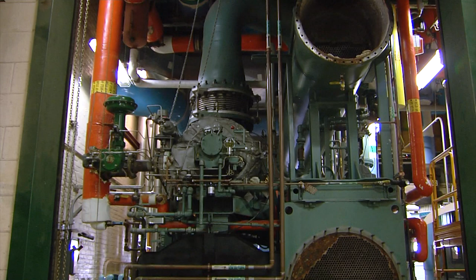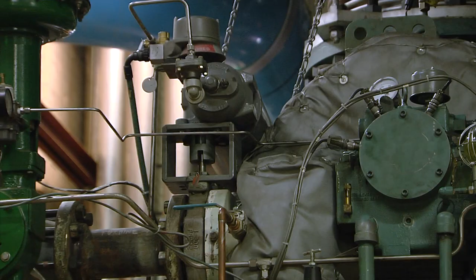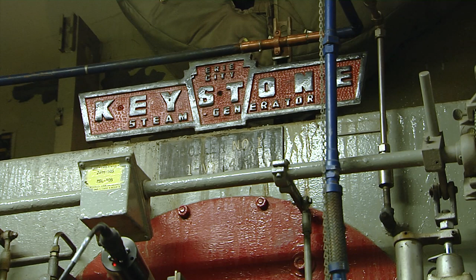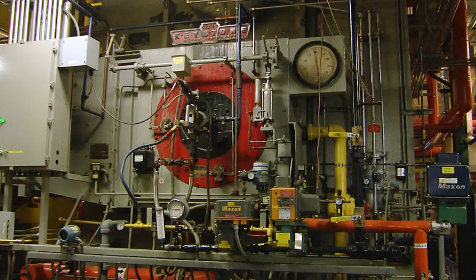So do these boilers need to run all year? Yes, we actually make air conditioning, chilled water, with our steam in the summertime. We have two steam-driven turbines here, the only two in the state—each are 1,365-ton chillers. We also have two steam absorption chillers in our health science research building, so we actually generate air conditioning with steam. Since our operating staff is here 24/7, 365, they're professional operating engineers who know how to handle equipment. The equipment we buy here is also industrial grade, as opposed to commercial grade like you'd put in a building, so these pieces of equipment could last 50, 60, 70 years with proper maintenance, as opposed to 20 to 30 years with building-centric equipment. That's another benefit of having a central plant.